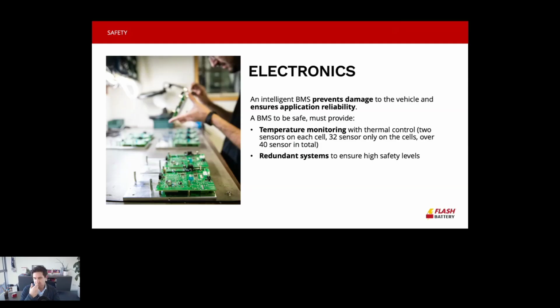Also, on the connections, if for a problem during production or during the battery's life a bolt is not tightened well, that creates a hot point, and it's really difficult to feel it if the sensor is maybe 20-30 centimeters away in the air. If we put it on the bus bar, we can feel exactly the temperature and prevent possible problems.